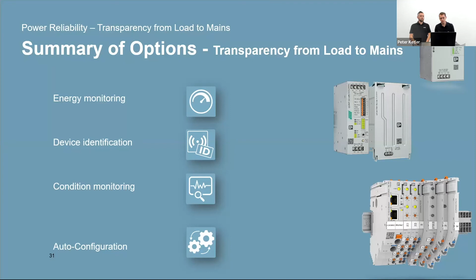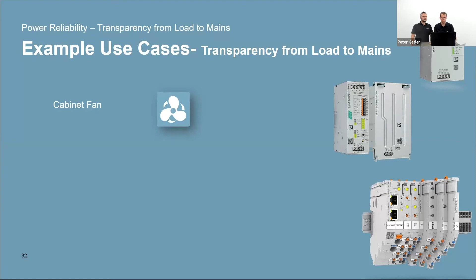One example is a cabinet fan. A lot of cabinets in warmer countries are cooled by a fan, which is important for the reliable operation of the application. When this cabinet fan becomes polluted or dirty, it becomes less effective, and another effect is that the current will rise in the cabinet fan. You can monitor that current over time to do preventive function monitoring for the fan.